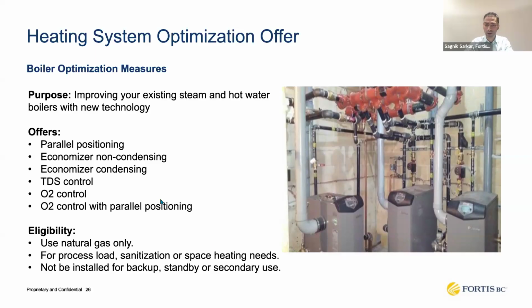Next, we have economizer, non-condensing. An economizer is just like a heat exchanger. Just imagine when your car engine gets hot, the heat is usually wasted on your car's bonnet or from the exhaust. A non-condensing economizer captures some of this exhaust gas heat to warm up the air going inside the furnace. Remember, the furnace needs air to burn the natural gas, right? So your air is getting preheated, which means that your efficiency goes up. So if you install this equipment, we provide incentives for that. Matt will go over the amount of incentives in his slides later.